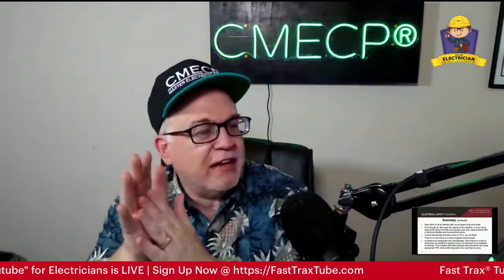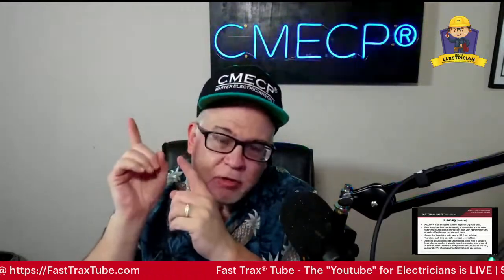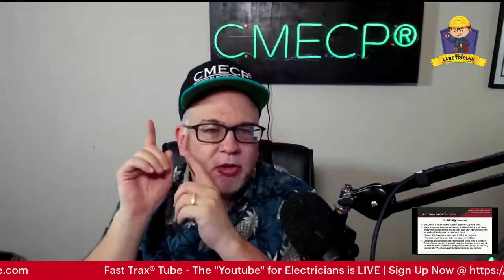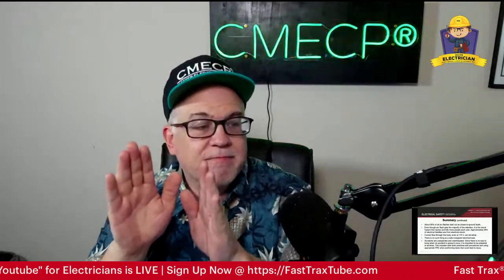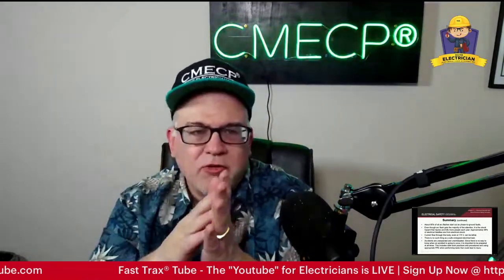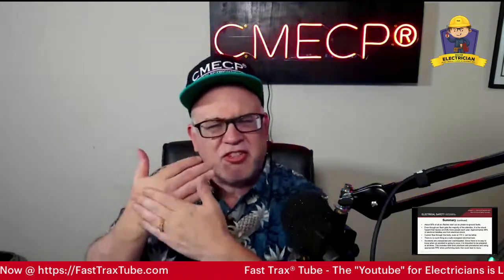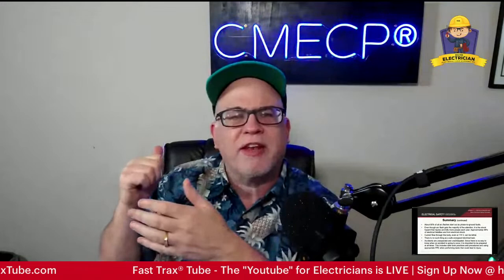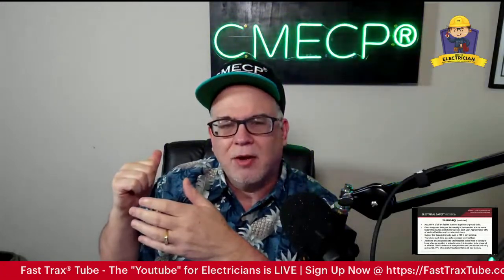There's no such thing as a safe, energized electrical test. Absolutely not - even that receptacle or ceiling luminaire you're going to replace, don't do it hot. There is no such thing as a safe, energized electrical test. De-energize it. There's no need to work on stuff live, Superman. You don't need to do it. You might say you're in a hurry, okay, whatever - but the moment something happens and you get shocked, even a slight shock, it might cause you to fall off the ladder and break your neck. Was it worth it?